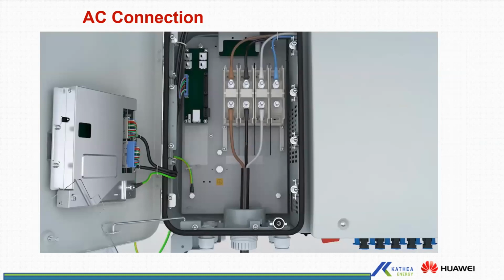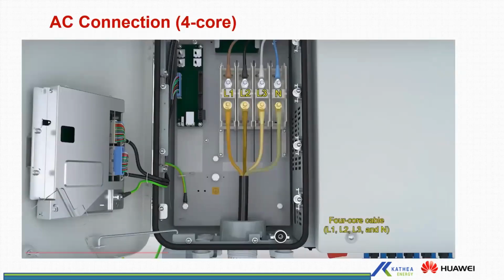If you open it, inside you get a block connector for your AC cable connection. The inverter supports 3-wire and 4-wire connections. So this is a 3-wire connection without neutral. Whenever you set a 3-wire connection, when you're doing the commissioning, you need to specify the type of wiring you have set. The inverter comes with default settings for a 4-wire connection, which is 3 lives and a neutral.